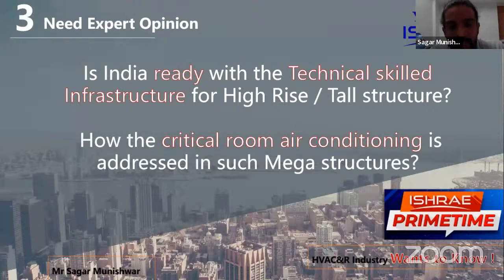When you design a very high-rise building, say 100 or 120 meters high, it's important to break the pressure in the systems. This means you need multiple service floors in between. For a chill water system in a building 180 or 200 meters tall, it becomes very difficult to sustain the pressure for the chillers and associated valves and peripherals, so you need a service floor in between, say at 70 or 80 meters.